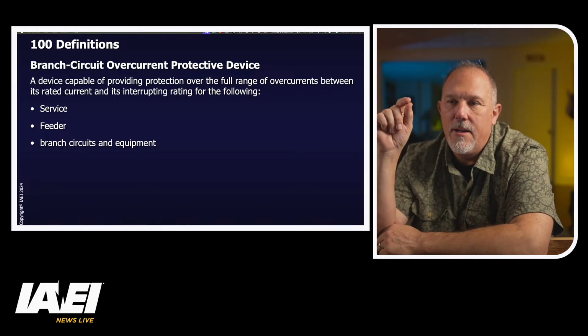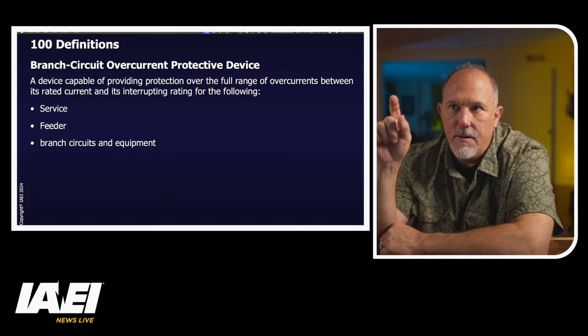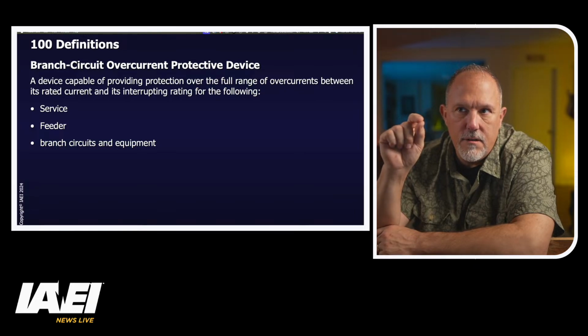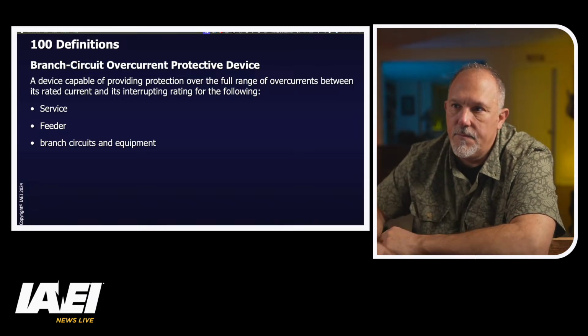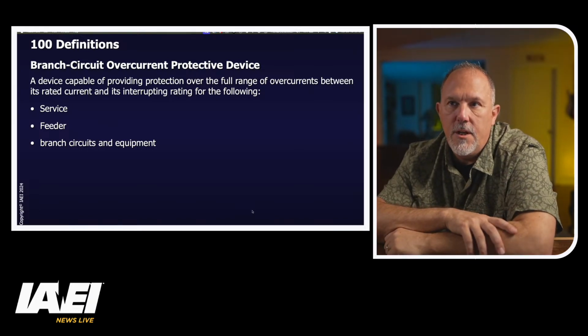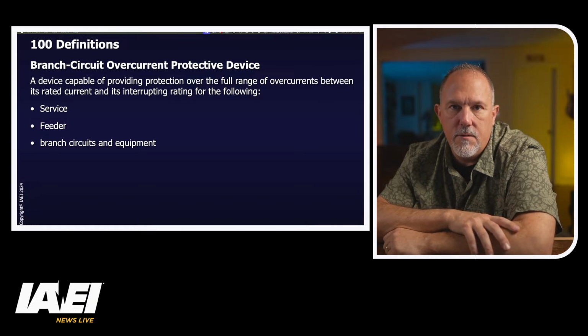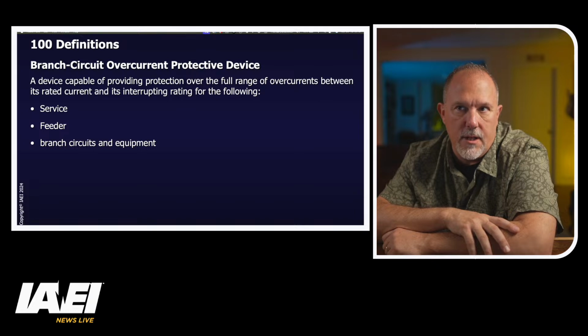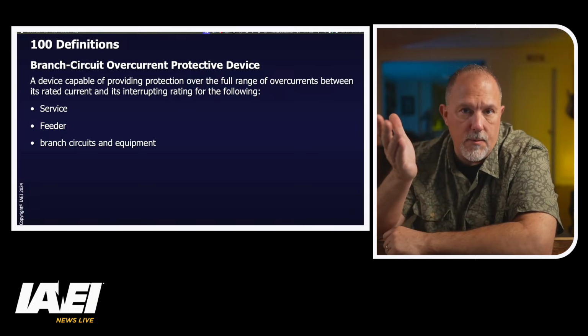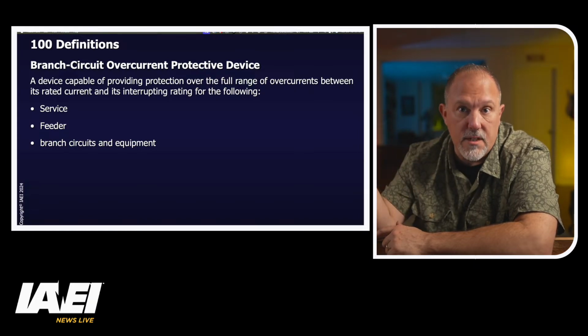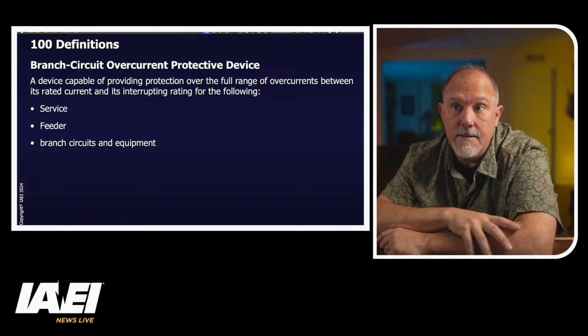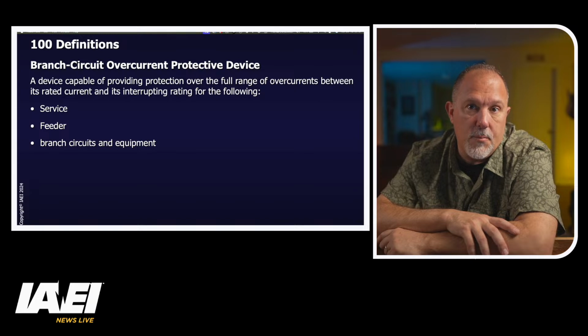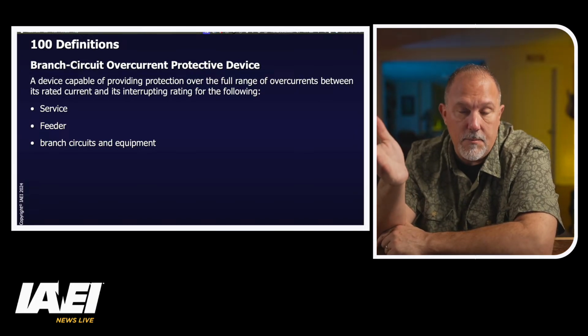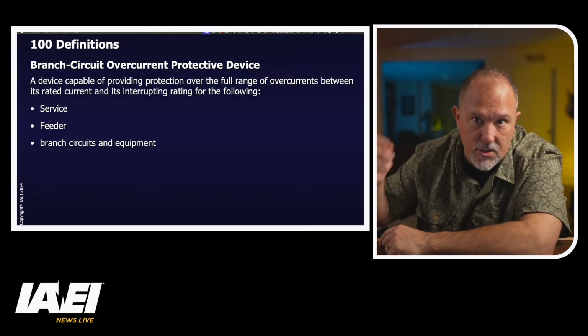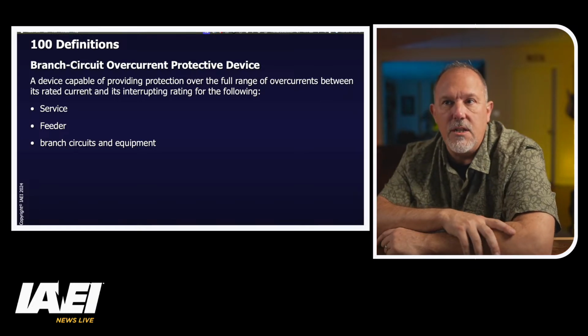I don't know why. But now, it says that it protects services, feeders, branch circuits, and equipment. And I've got to break out the equipment. So it protects those four items: services. And remember, if you look at the definition of what a service is, it includes a lot of different components. Feeders, we just saw what the definition of a feeder is. It's everything between sources, and we're going to talk about those here in a second, and the final branch circuit overcurrent device, which could be another feeder. It doesn't have to be a branch circuit. It doesn't have to be the beginning of a branch circuit. Make sense? So it's all the conductors in between.